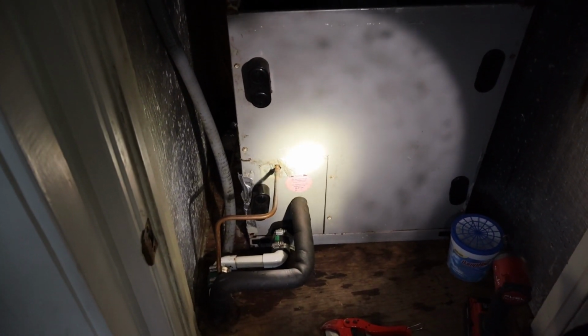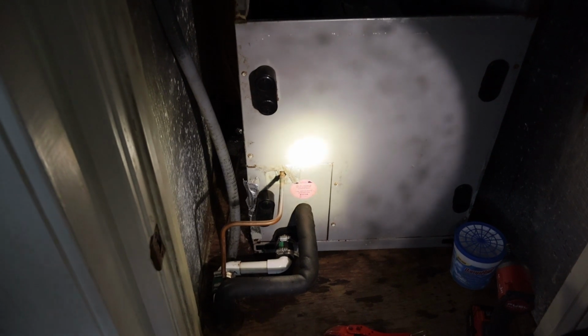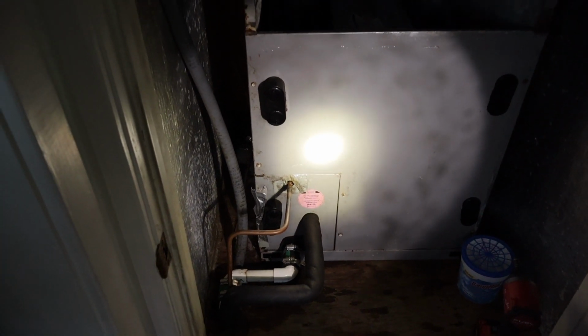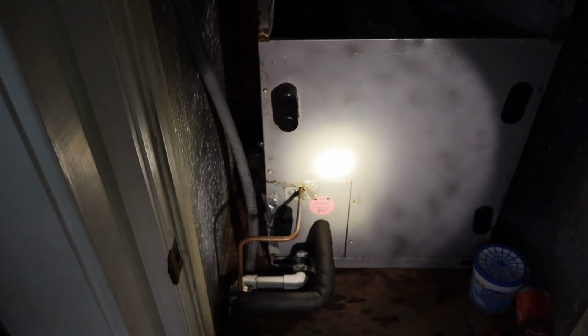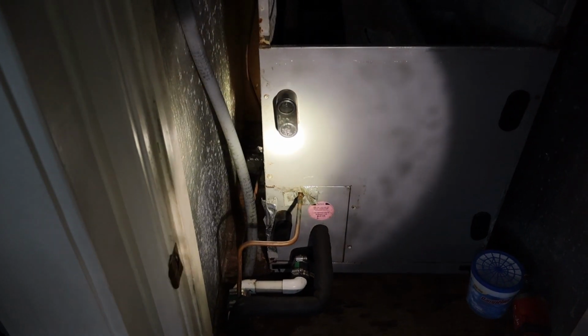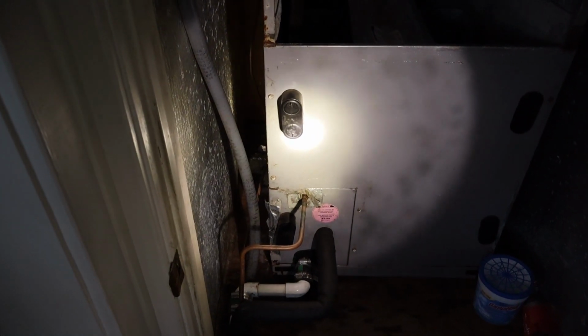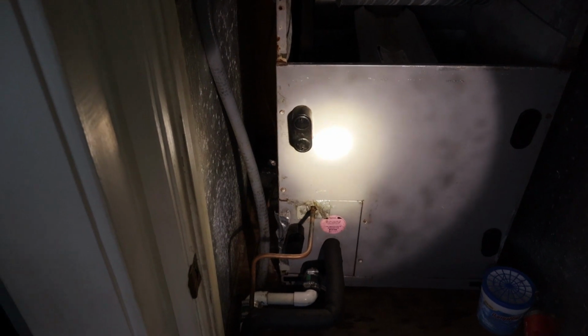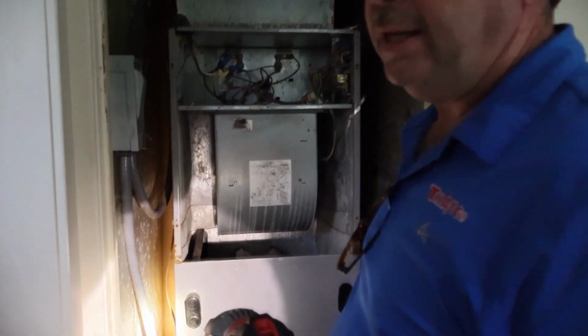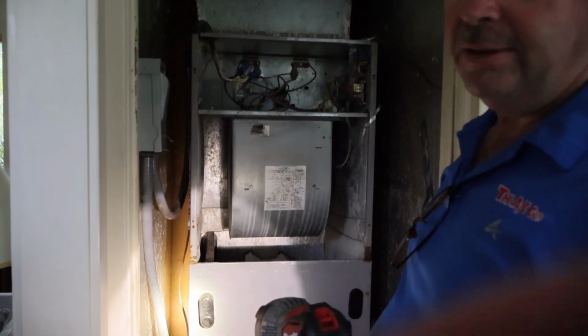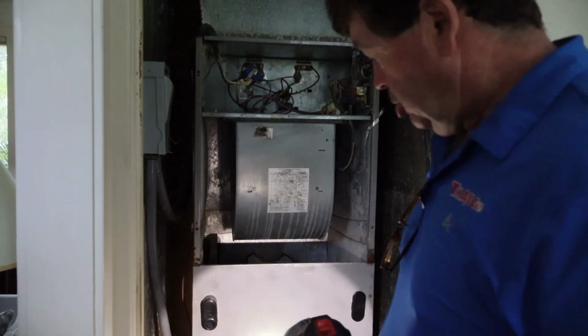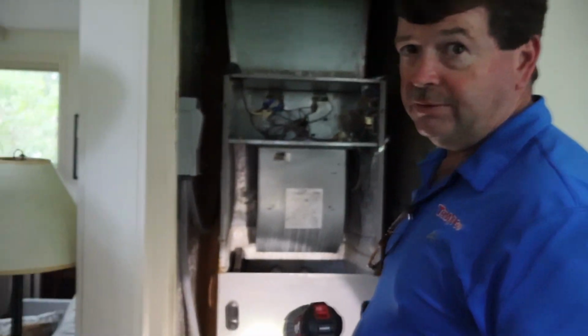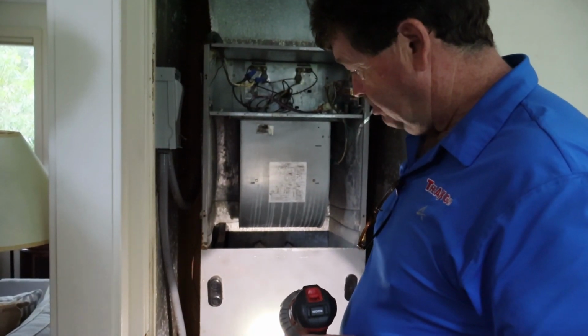If this was in an attic horizontal application, we'd be looking at pans. Make sure there's no rust in the pans. Make sure the safety pan can handle the water and goes the right direction. Make sure we don't have plenums that are too small, or too large rather, excuse me. If they're larger than the air handler, it's problematic. So you've got to make the customer aware of these things. If it's got a secondary drain on it, make sure it exits the soffit, as we talked about outside.